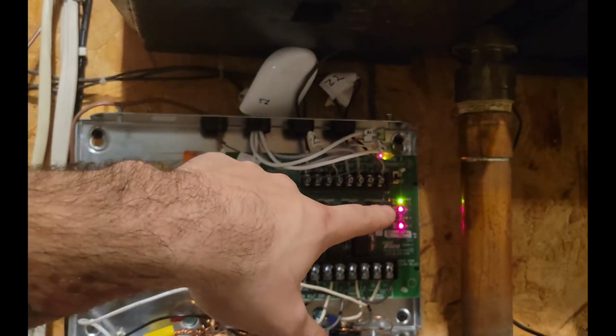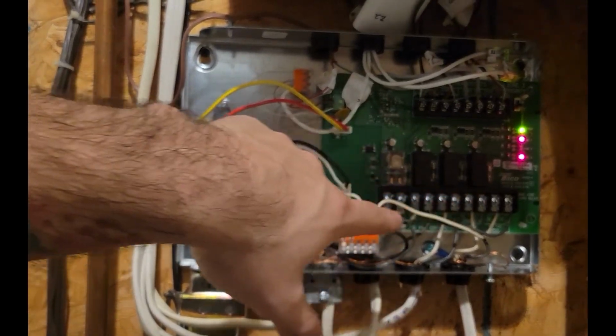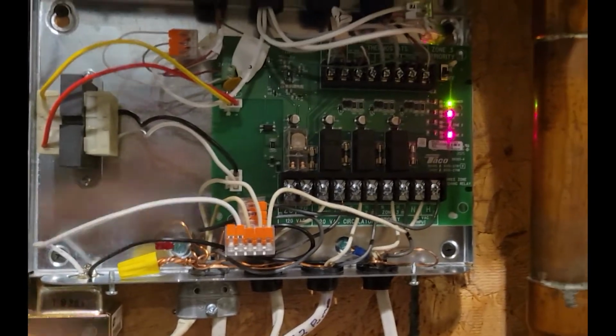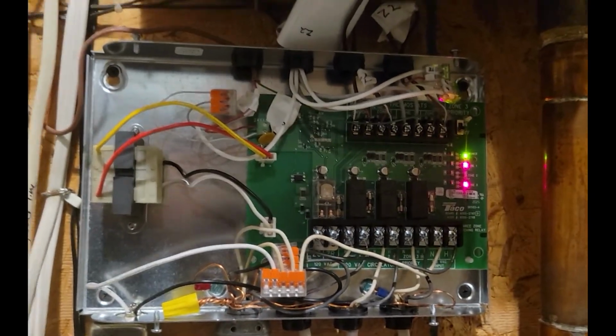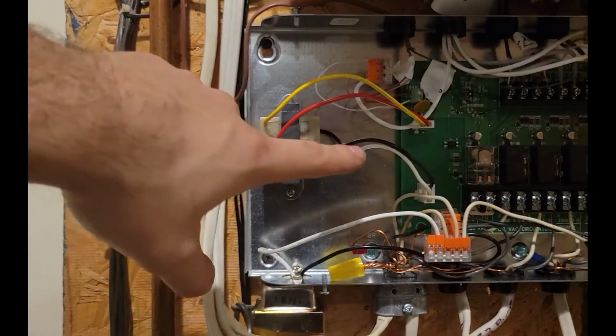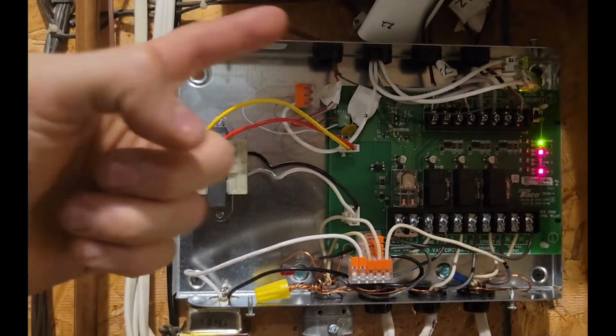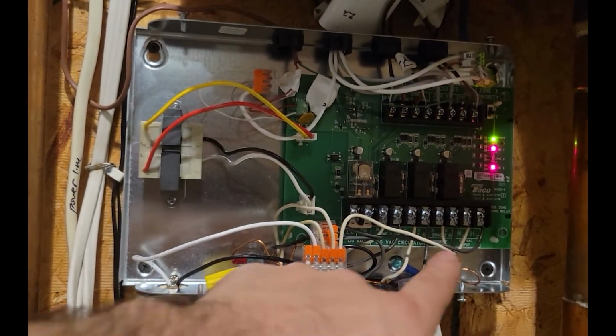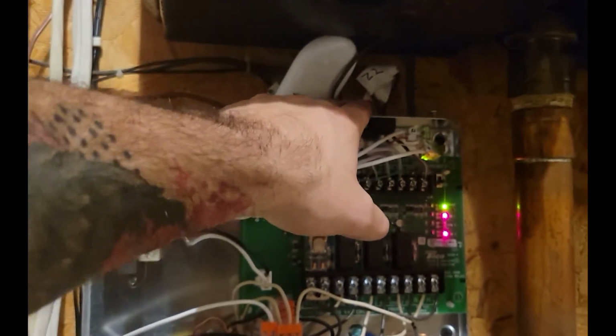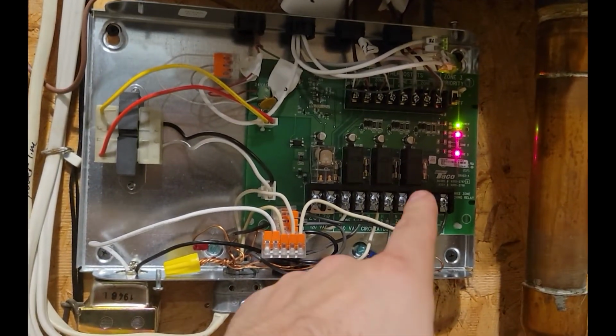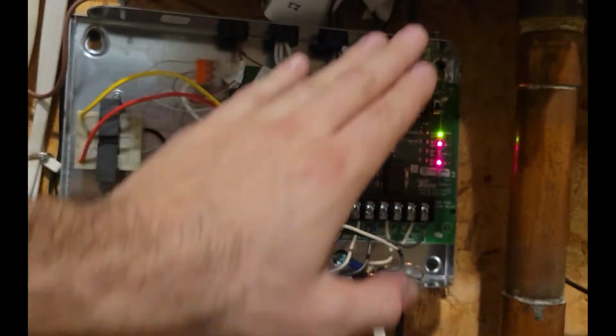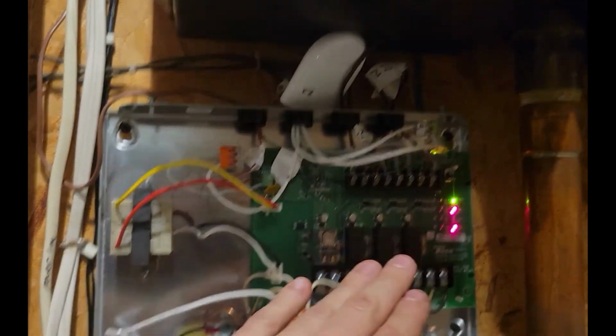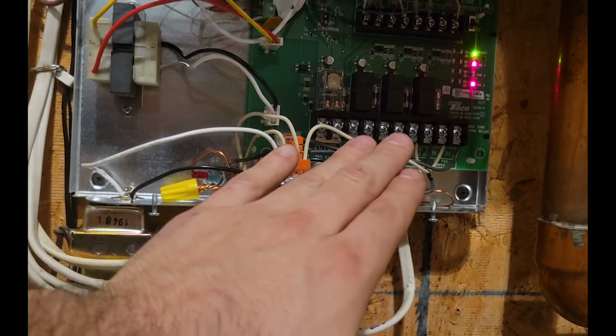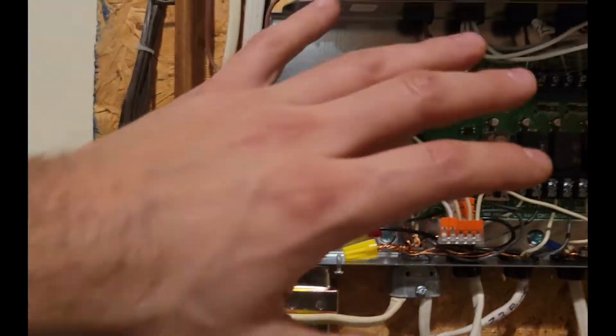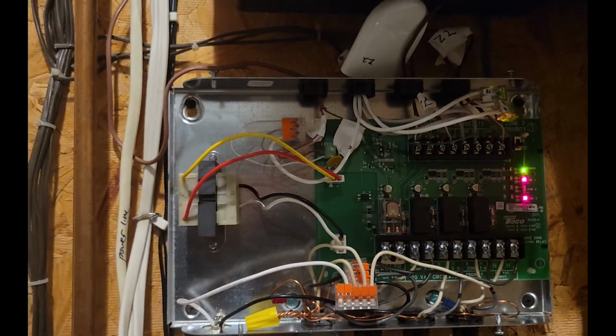So right now we have two zones calling for heat. We have the high voltage terminals here on the bottom. They're actually energized based on the call for heat right now. So basically, you have 120 volts coming in, and we transfer 24 volts out to the top portion. The top is low voltage, the bottom is high voltage. So based on each individual thermostat call, the appropriate zone pump will trigger. That's telling you, okay, zone 2 is calling for heat, so zone 2's pump is going to start to circulate that hot water. So I rewired it. It was actually a mess in here. It looked quite bad.